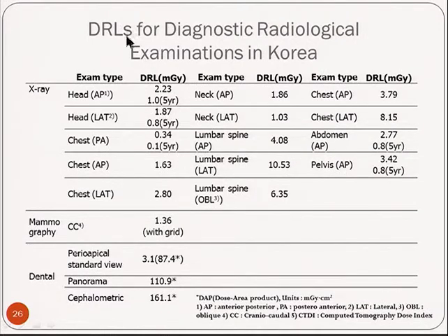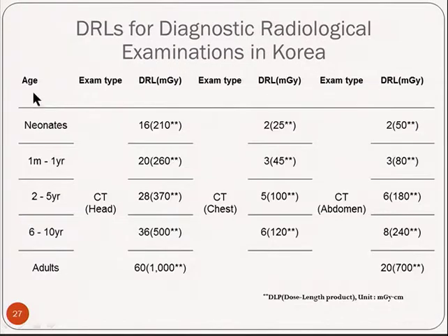These numbers are DRLs for diagnostic radiological examination in Korea, and we have X-rays, mammography, and dental imaging. And DRLs for CT scanning for pediatric and adult patients already exist.